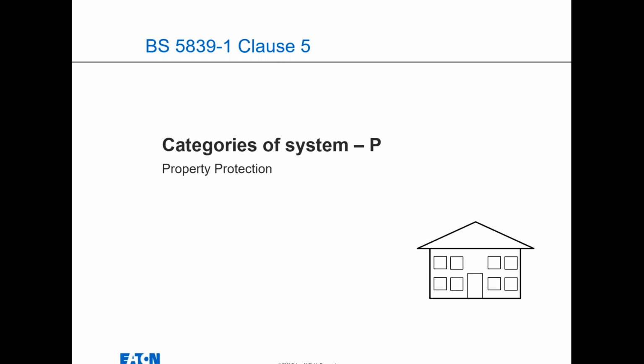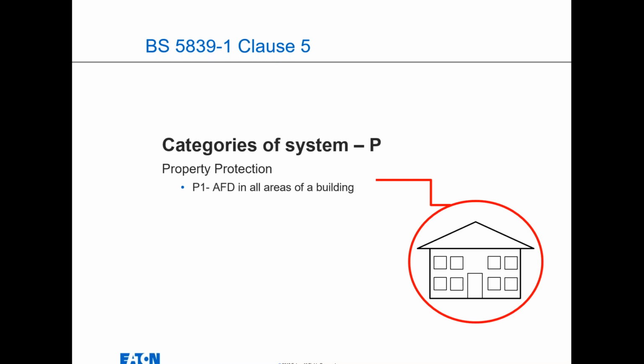So as we say, categories of system, you've got P for property, and in my experience, it sometimes starts off as a P system. It might be in a document somewhere, and it generally moves into an L system as you get into more of the detail, because property protection is very few and far between when you've got nobody in the building. There are certain jobs I've done in the past where you've got, for instance, high expensive works of art, so you've got nobody in the building and it's just purely protecting the asset, and therefore you can get away with a different level of detection, or sounders and call points can be omitted because you're not trying to evacuate the building.